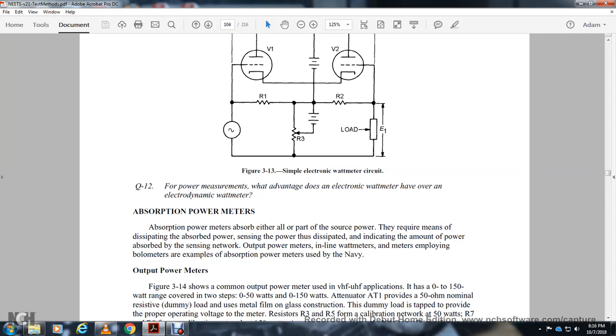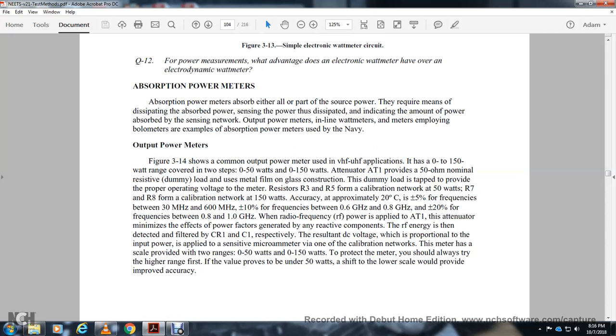Absorption power meters absorb all or most of the power from the source and measure the dissipated power. The Navy output power meter is one example of an absorption power meter. Figure 3-14 shows a common output power meter for very high frequency applications, with a range of 0 to 150 watts covering ranges of 0-50 W and 0-150 W. Attenuator AT1 provides a 50-ohm nominal resistance dummy load using metal film in glass construction. Resistors 3 and 5 form the calibration network at 50 watts; resistors 7 and 8 form the calibration network at 150 watts.